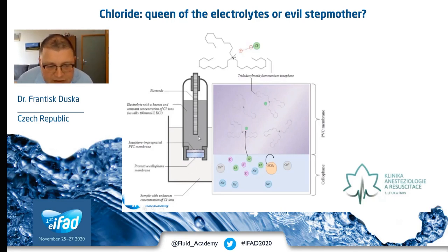This penetration is facilitated by a molecule called an ionophore. Usually the structures are not published. It's an industrial secret of the acid-base analyzer manufacturers, but it is very relevant to what extent this ionophore is selective, because if it is not selective, other anions like bicarbonate may cause falsely high chloride readings and therefore inaccuracy.